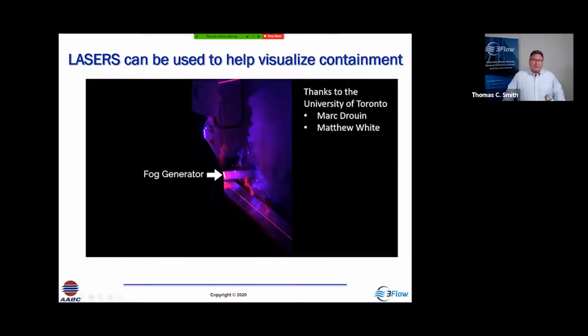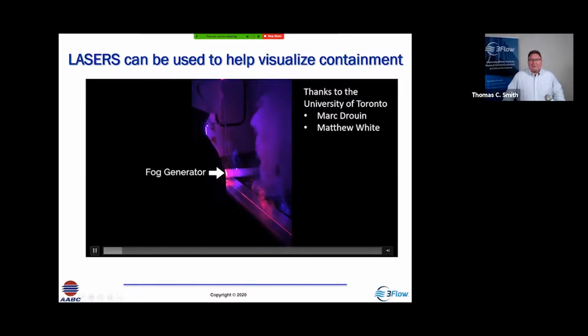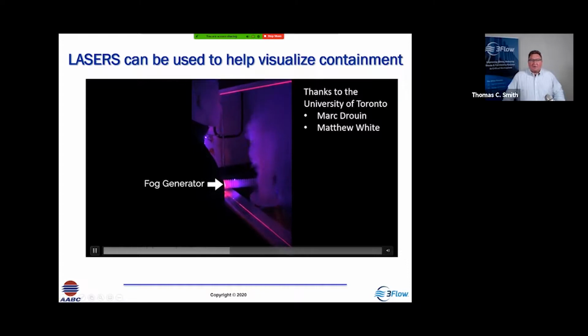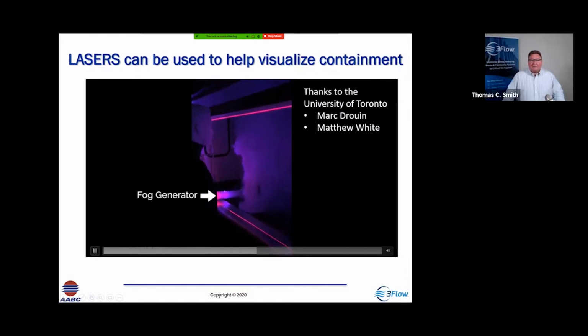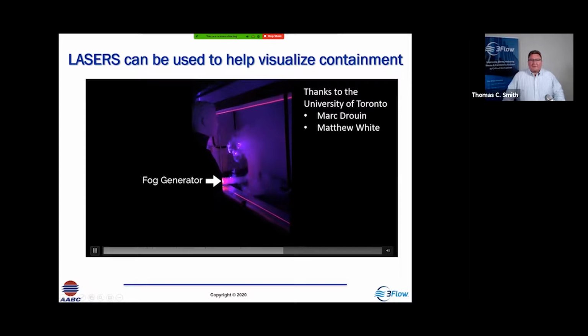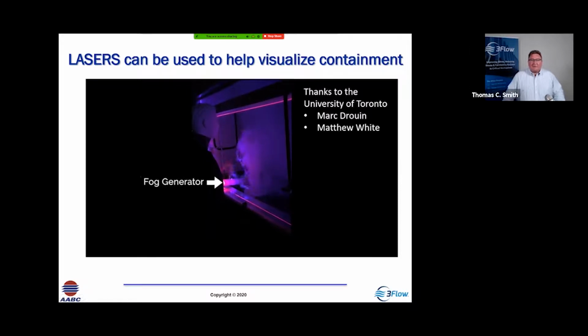Working with the University of Toronto, they came up with a way to visualize airflow patterns using a series of lasers, creating a laser plane at the plane of the sash, allowed to look at the containment. And so we're looking at concentrations as they break the plane of the sash. The red is at the plane of the sash, and anytime it shows red, that means smoke is coming through that plane out of the hood. And so it's kind of an interesting test to visualize the airflow patterns in this way, and we learn a lot about the factors that influence hood containment.